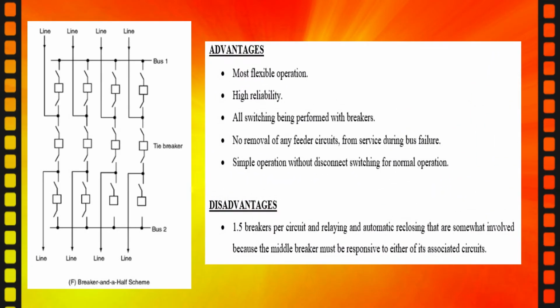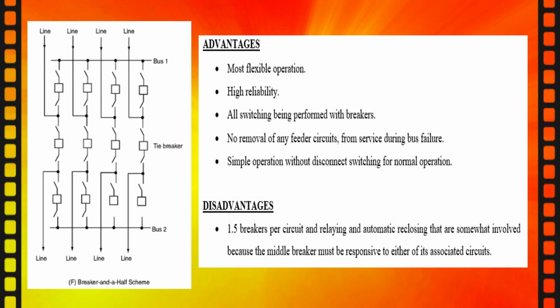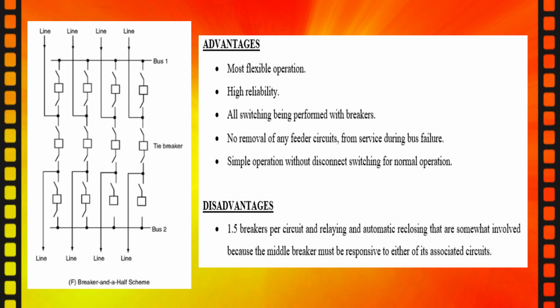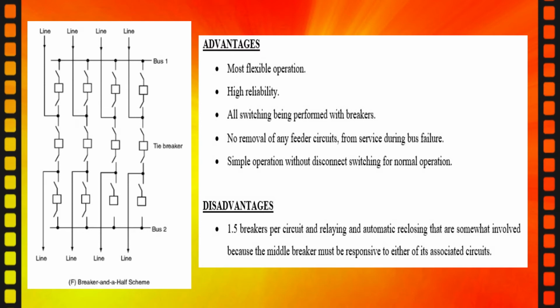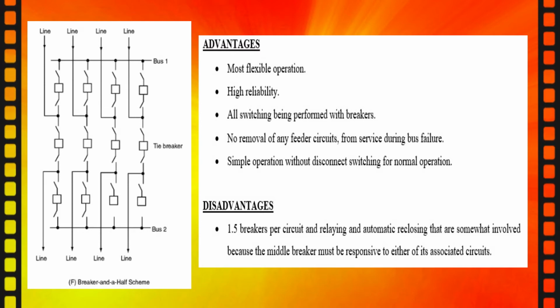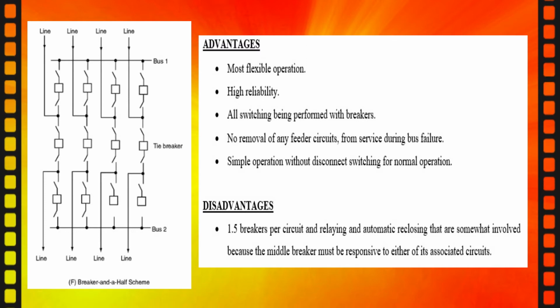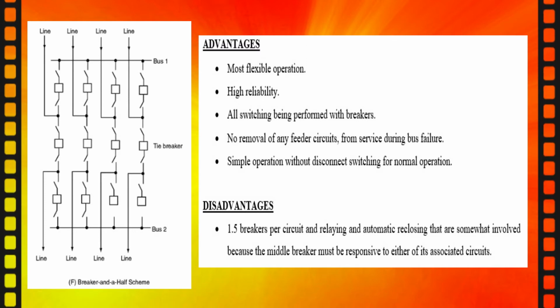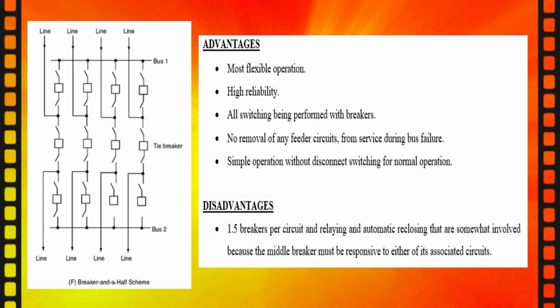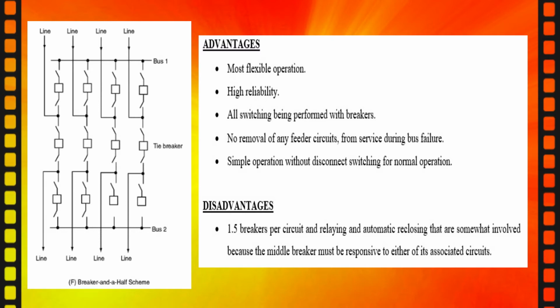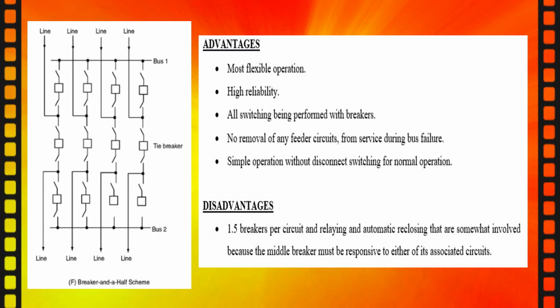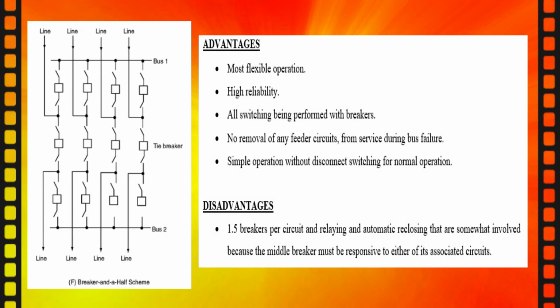Okay, the next diagram is the breaker and a half diagram. The advantage is most flexibility in operating, high reliability, all switching being performed with breakers, and no removal of any feeder circuit from service during bus failure. It's also simple operation without disconnecting switching for normal operation.